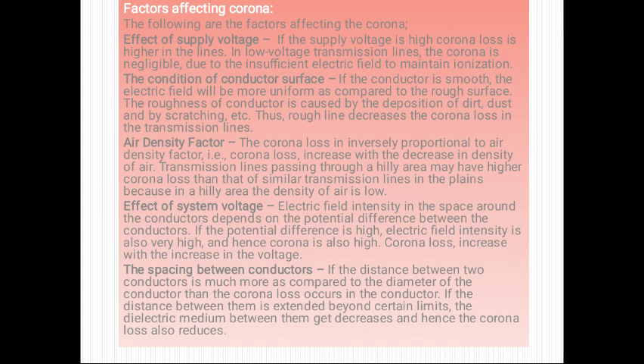Second is condition of conductor surface. It means if the conductor is smooth, the electric field will be more uniform as compared to a rough surface. The roughness of a conductor is caused by the deposition of dirt, dust, and by scratching etc. Thus, a rough line increases the corona loss in the transmission lines.